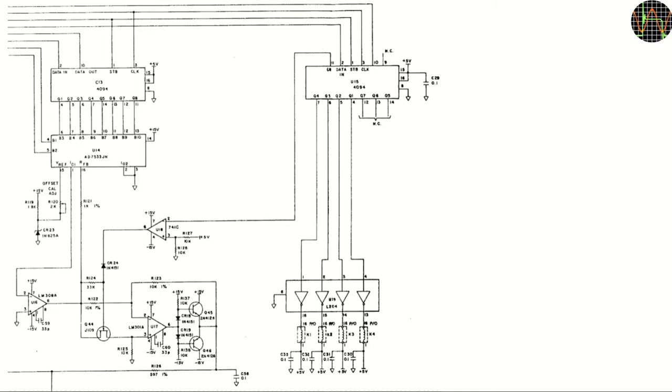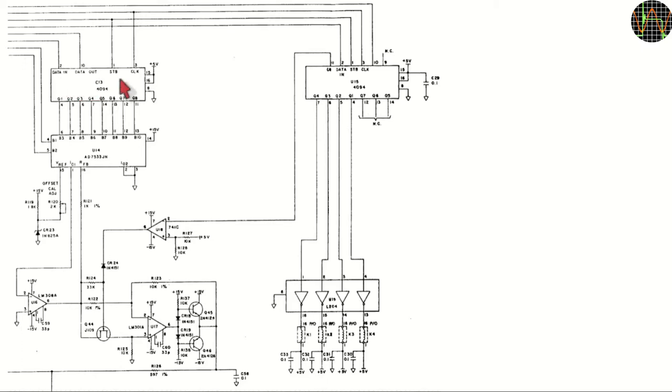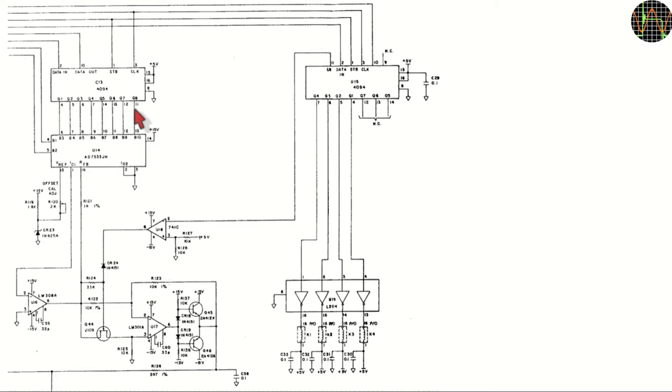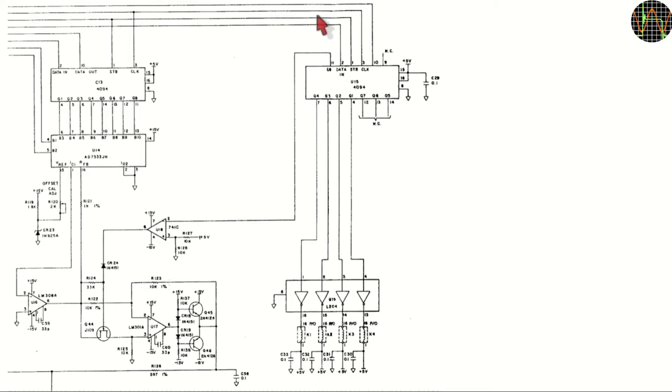Without going into details, this is the main part of the schematics dealing with the signal offset. The circuit is located on the final amplifier board, not the main board. The CPU sends the desired offset as a serial data stream and a clock signal to the 8-bit shift register, a 4094. Once the desired data has been sent, the CPU activates the strobe signal which copies the new data in the shift register to the internal 8-bit memory of the 4094 and makes it appear on the 8 output pins Q1 to Q8. So this part works to convert the serial data into parallel data. The 8201 uses this method all over the place. You can see an example of the same kind on the right, which deals mainly with attenuation. In this case, the clock and strobe lines are connected to the other 4094 but the data lines are different, which means the shift register will contain different values when the common strobe signal happens.